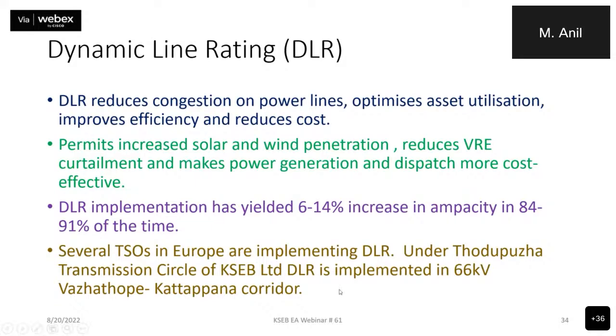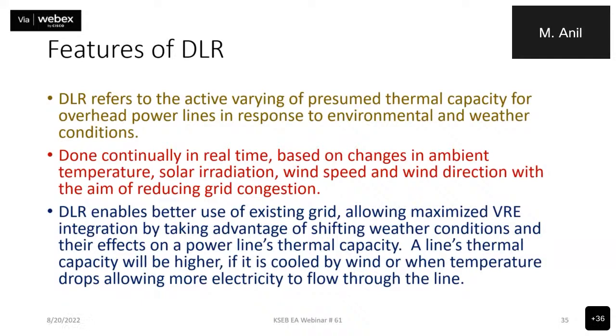Features of DLR. What dynamic line rating achieves is it refers to active varying of presumed thermal capacity for overhead power lines in response to environmental and weather conditions, done continually in real time based on changes in ambient temperature, solar irradiation, wind speed, and wind direction, with the aim of reducing grid congestion. Dynamic line rating enables better use of the existing grid, allowing maximized VRE integration by taking advantage of shifting weather conditions and their effects on a power line's thermal capacity. A line's thermal capacity will be higher if it is cooled by wind or when the ambient temperature drops, allowing more electricity to flow through the line. This characteristic of the line, as regards its thermal capacity, is being utilized in dynamic line rating.